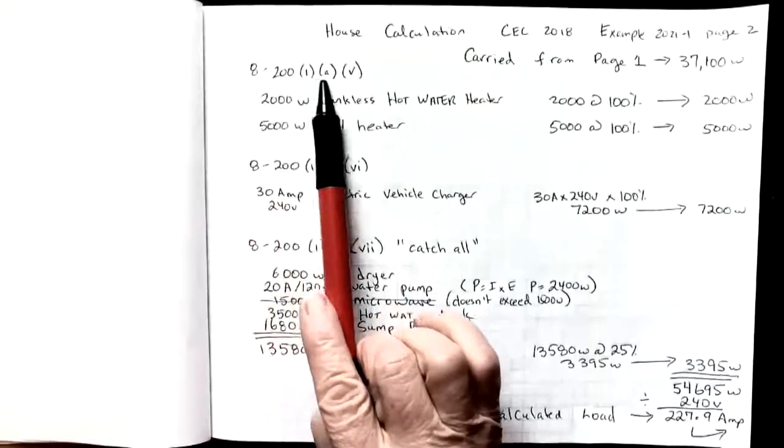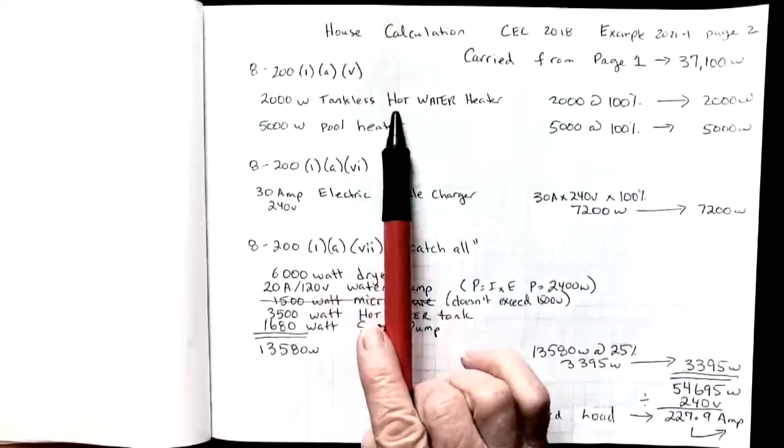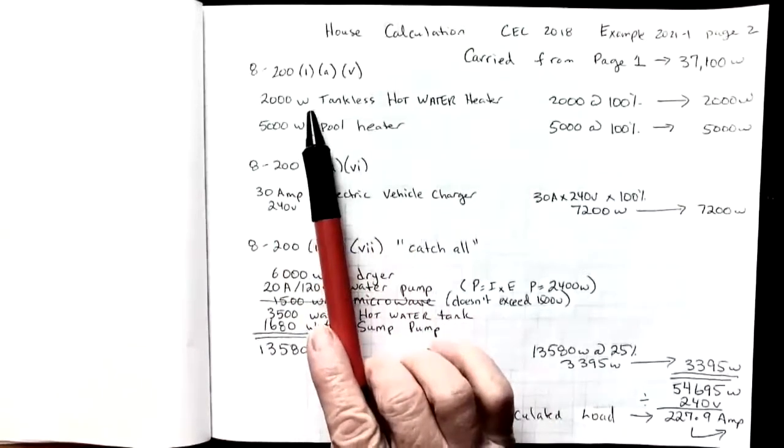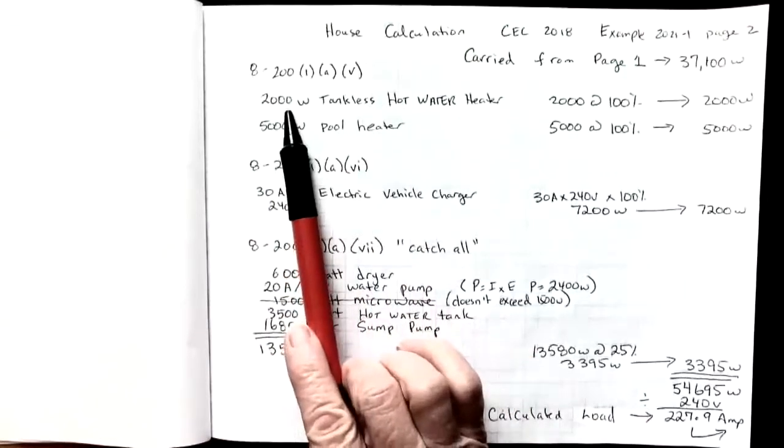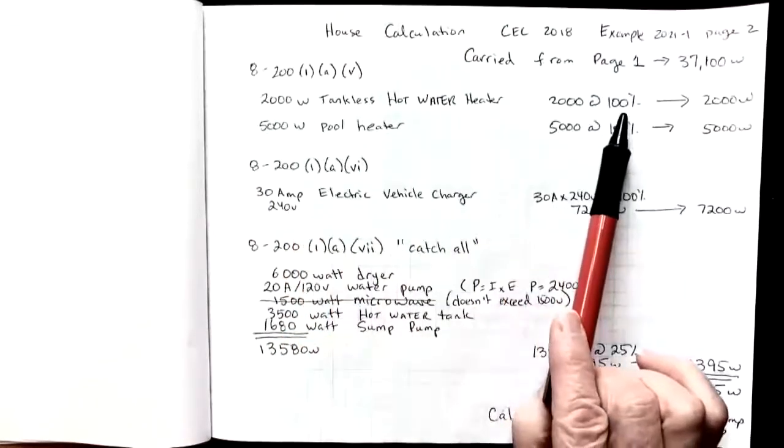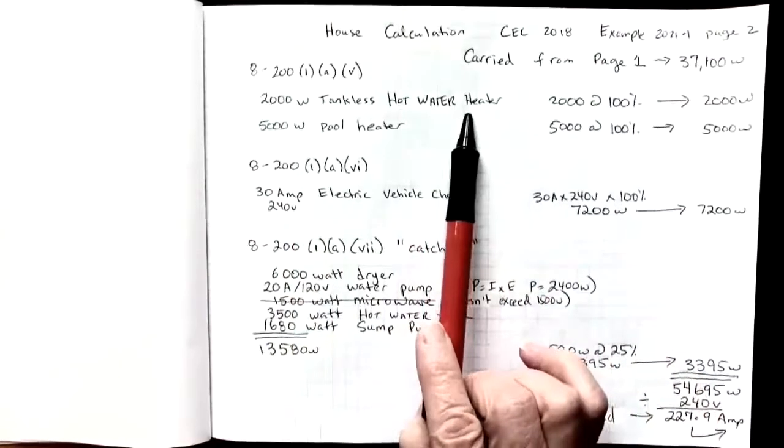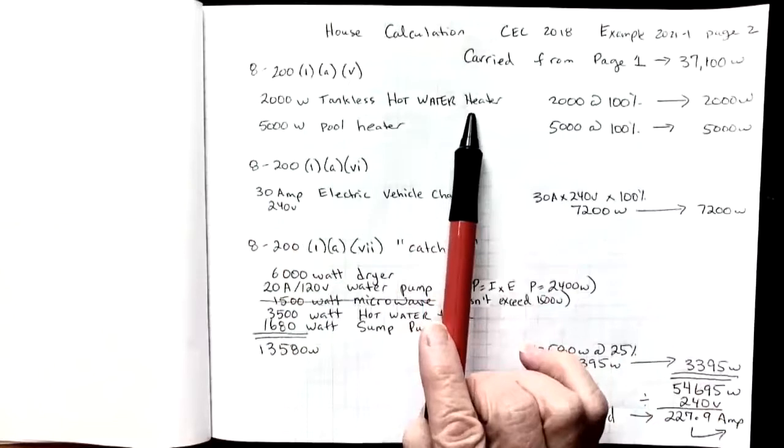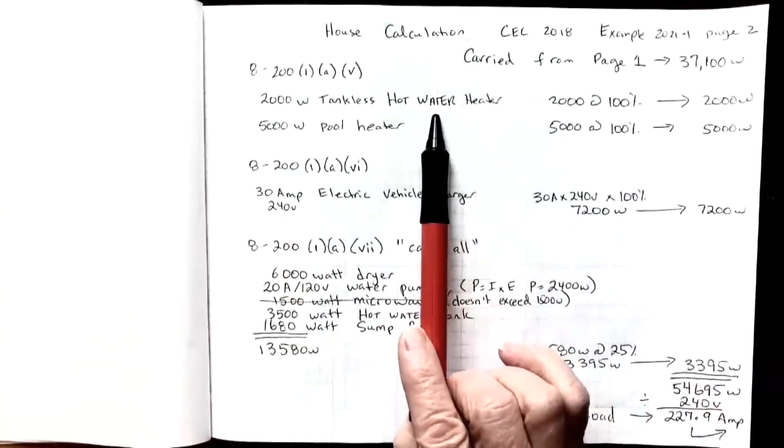Rule 8-200(1)(a)(5) speaks about a couple things that we have in this house. One is a tankless hot water heater, 2,000 watts, and we're going to take that at 100%. Remember a tankless hot water heater, even if it was under 1,500 watts, it would still fall in this rule and not in the catch-all rule, so we'd take it at 100%.